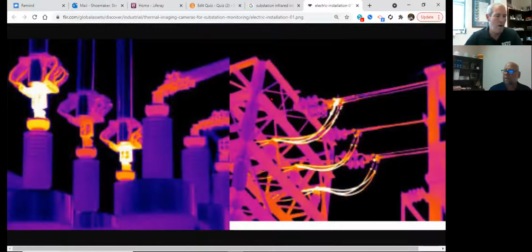Remember, when you're out there in the world, don't tighten something up and just hand tighten it — use a tool, make it tight. That lowers resistance. You're not going to splice one conductor with another until you clean it first. They actually do this out there, even when it comes off the reel — on a brand new installation, you need to scrub the conductor even after it's sat on the reel for a while. They are very proactive about it. Resistance is the utility's arch nemesis.